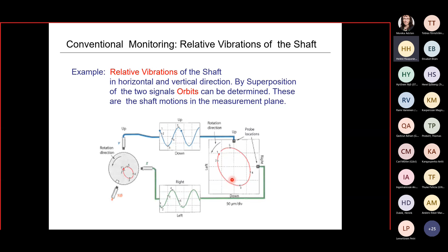But if we do a superposition of these two signals in vertical and horizontal direction, we come to an orbit where time is a parameter along this orbit. You can consider this orbit as, when you look along the shaft line, the axis of the shaft, you see the vibrations at this special location where you measure. This is also something considered in monitoring.